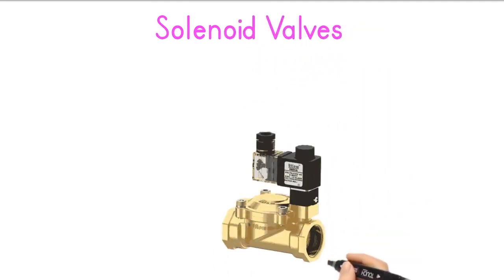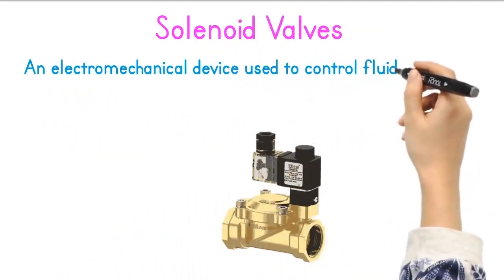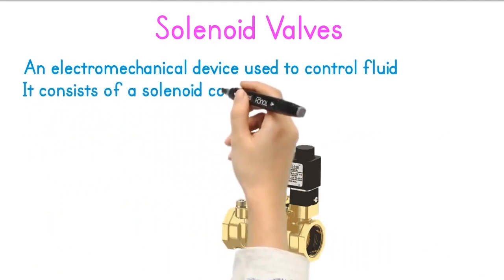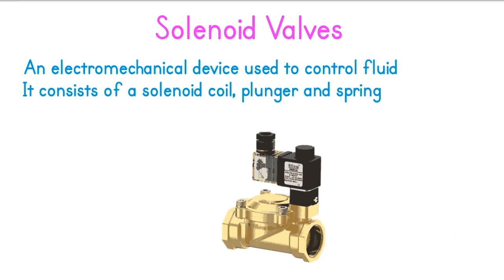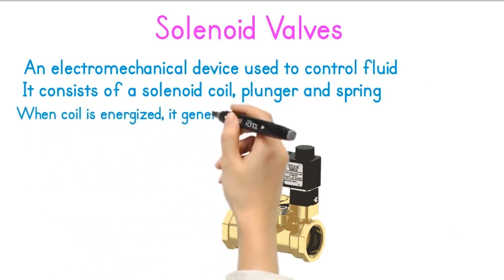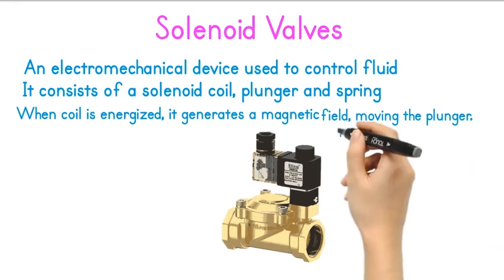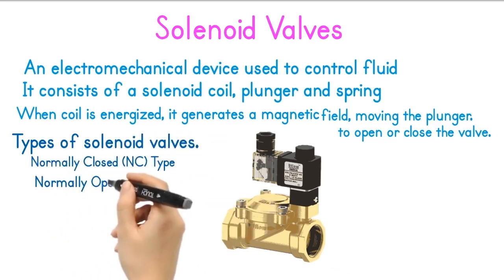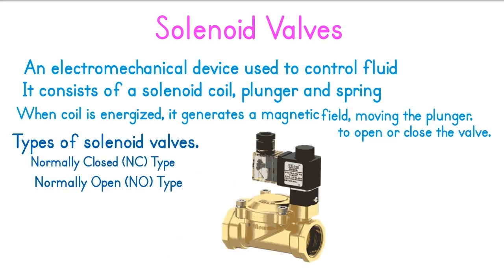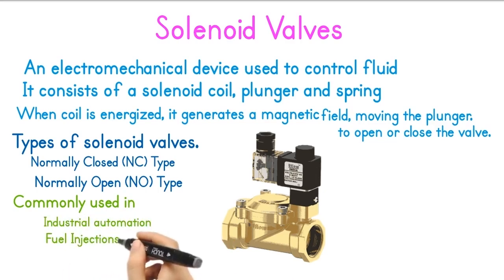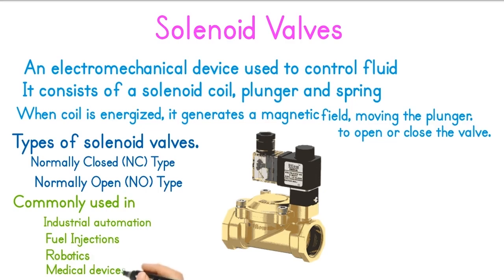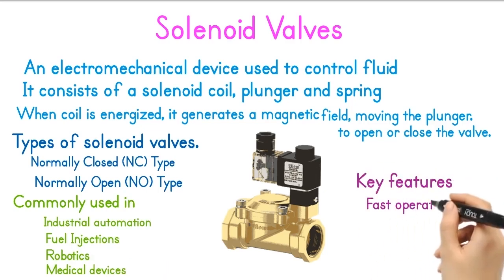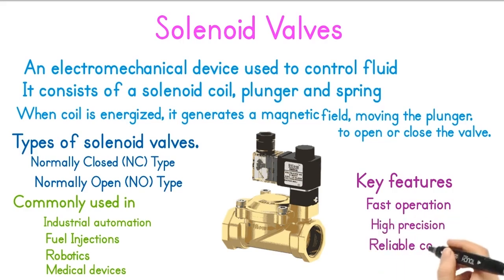Solenoid valves. A solenoid valve is an electromechanical device used to control fluid flow. It consists of a solenoid coil, plunger, and spring. When the coil is energized, it generates a magnetic field, moving the plunger to open or close the valve. There are two types: normally closed (NC) and normally open (NO). Solenoid valves are commonly used in industrial automation, fuel injection, robotics, and medical devices. Key features include fast operation, high precision, and reliable control.